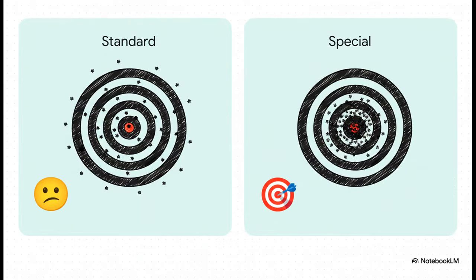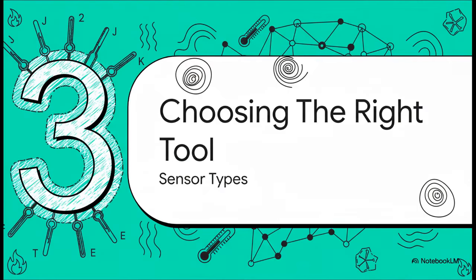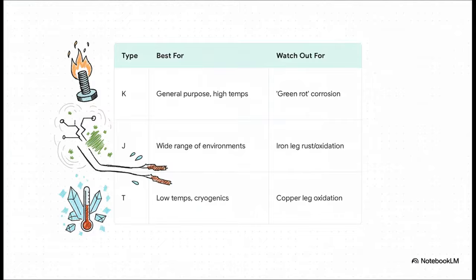And this is exactly why your choice of sensor matters so much. Look at this. If we had just started with that higher grade special limit sensor, its tolerance is much tighter. The math gives us an error of just plus or minus 3.2 degrees. You've literally cut your potential for error almost in half, just by choosing the better tool right from the start. But it's not just about getting a high-grade sensor. It's about getting the right type of sensor for the job you're doing. Using the wrong kind of thermocouple is a classic mistake. So let's run through the main options real quick. First, you've got what we call the base metal thermocouples. These are your everyday workhorses. Type K is the king.